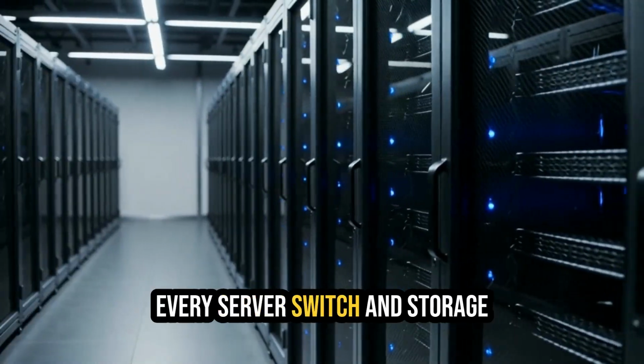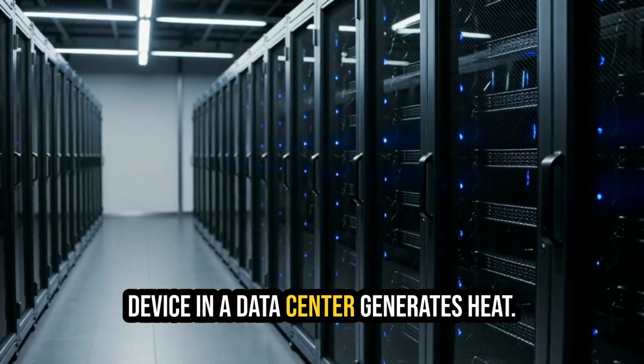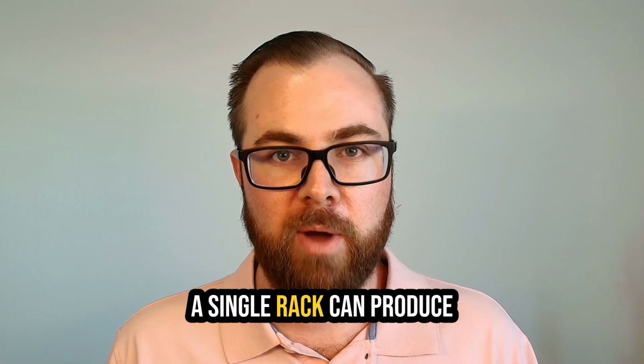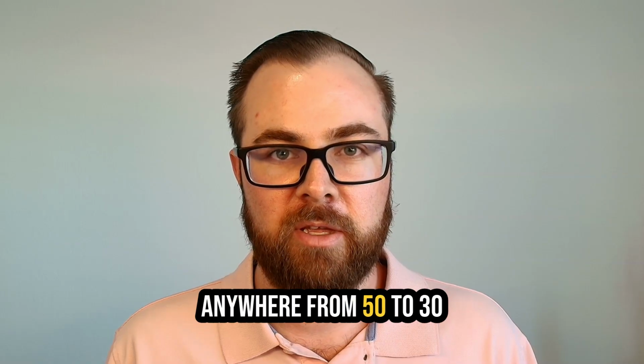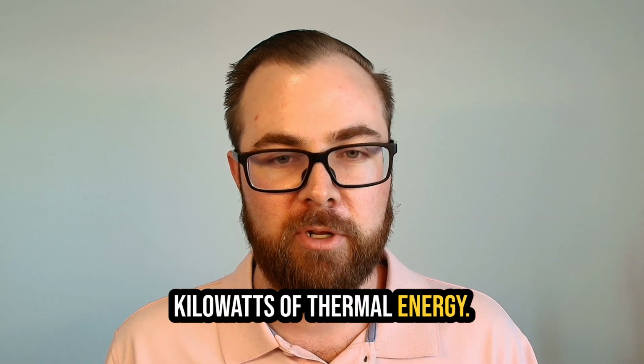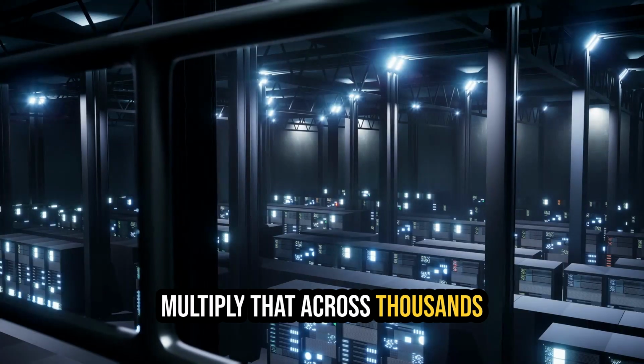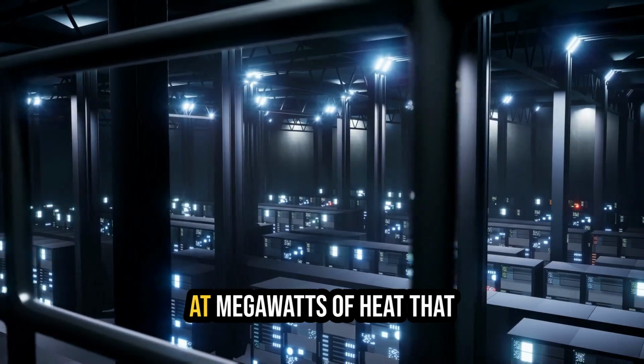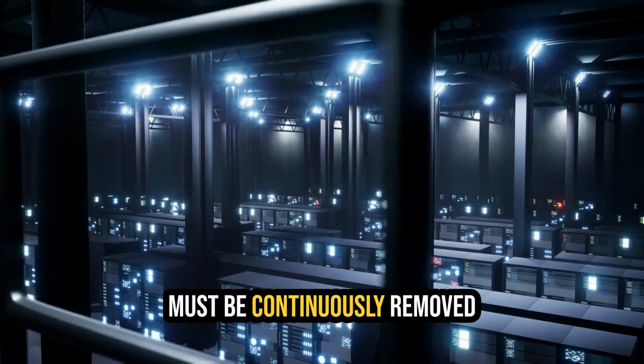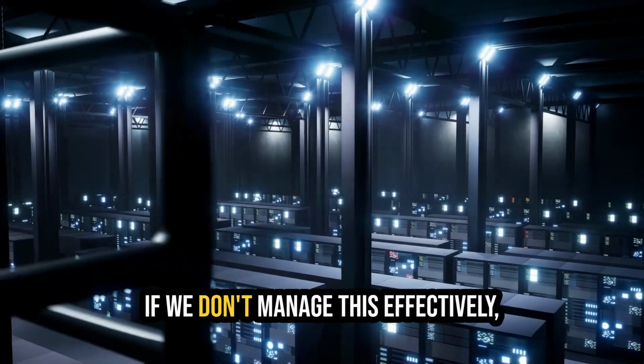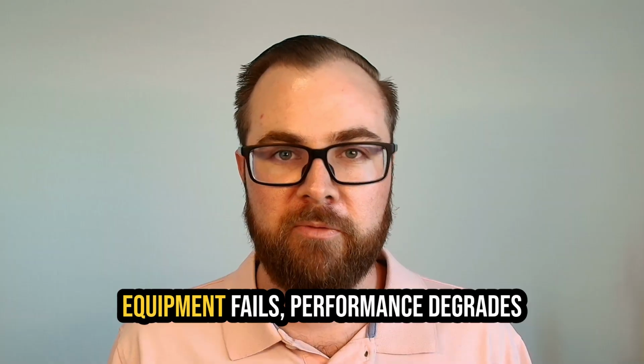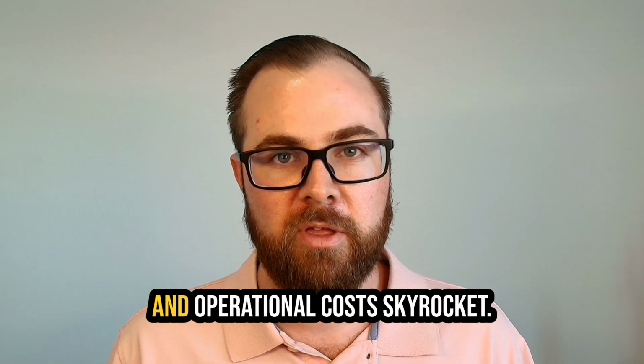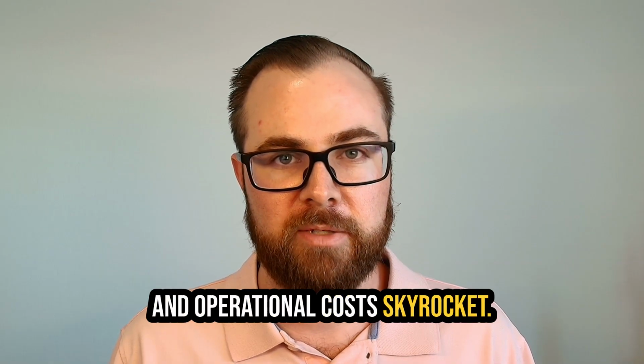Every server, switch, and storage device in a data center generates heat. A single rack can produce anywhere from 5 to 30 kilowatts of thermal energy. Multiply that across thousands of racks, and you're looking at megawatts of heat that must be continuously removed. If we don't manage this effectively, equipment fails, performance degrades, and operational costs skyrocket.